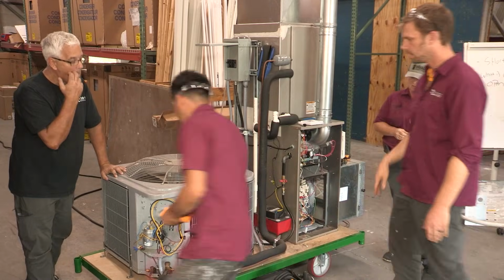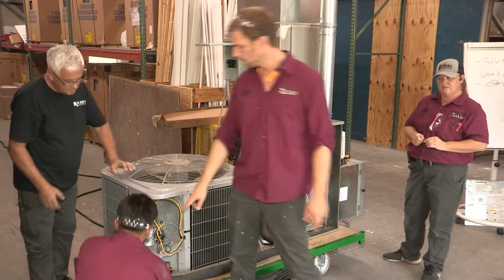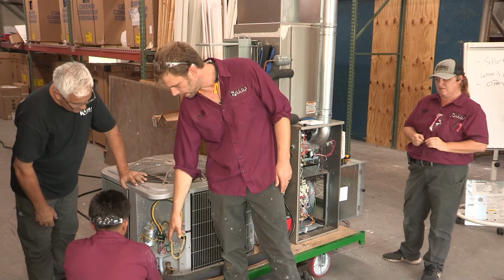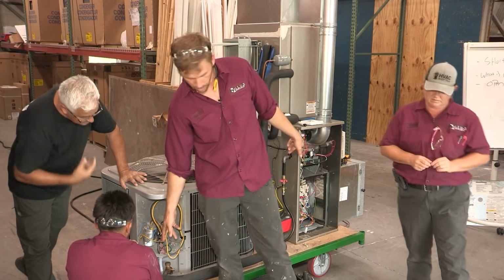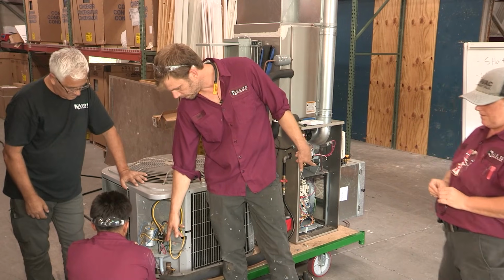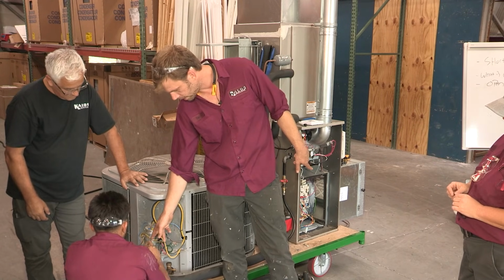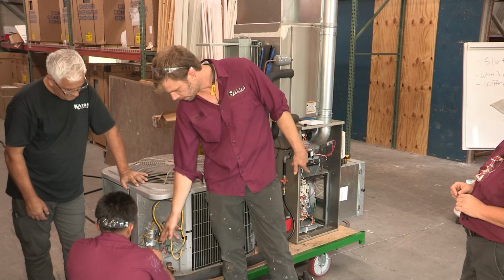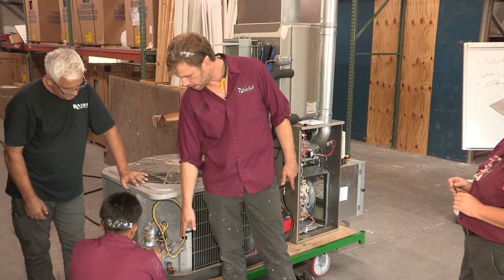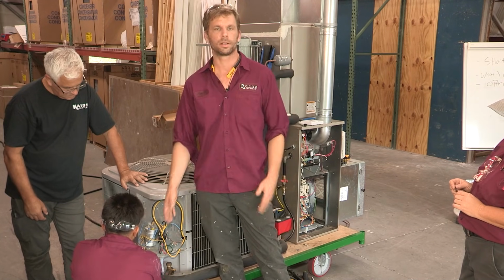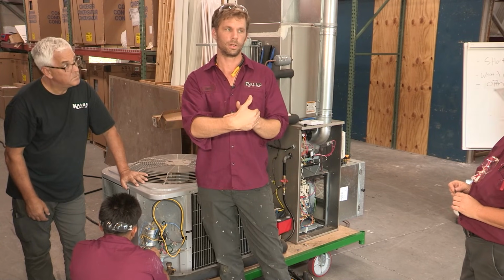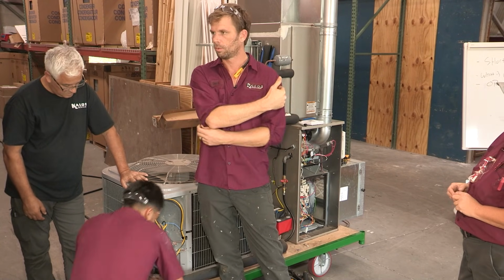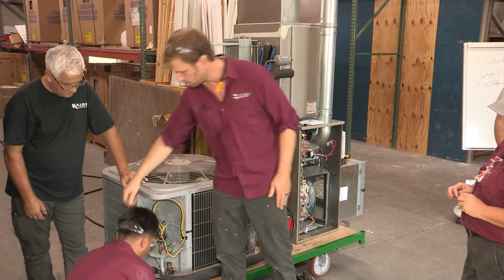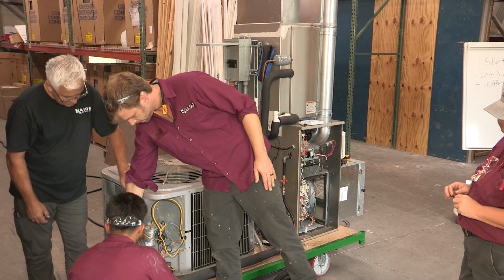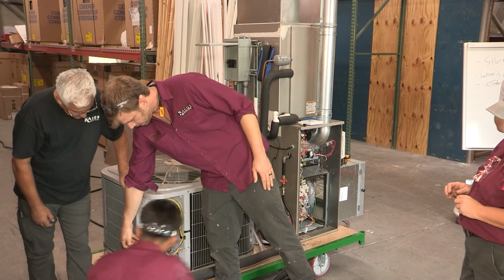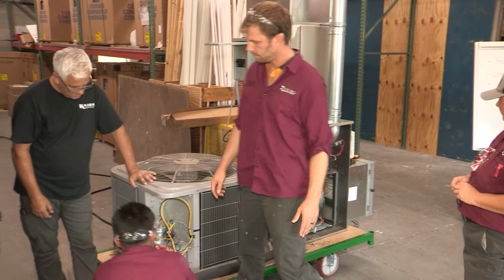Okay, so now listen, in most of your systems, common is going to be tied into ground at the transformer. So if you leave common hooked up on the circuit like it is right now, then you're going to get a path to ground when you check yellow to ground, because it's actually going to travel through your load and back to where it's grounded. So you're going to want to disconnect common during this test so you can actually see what's going on there.